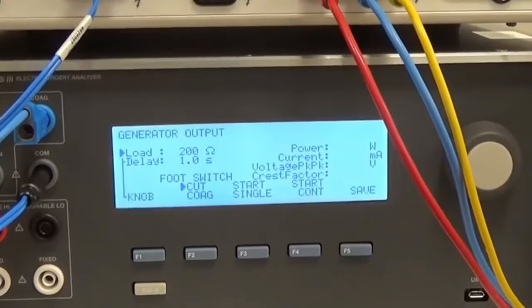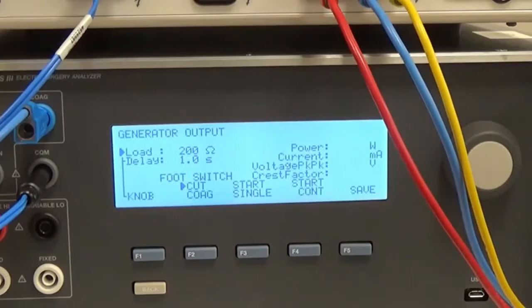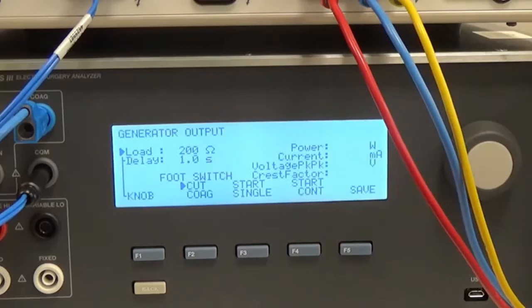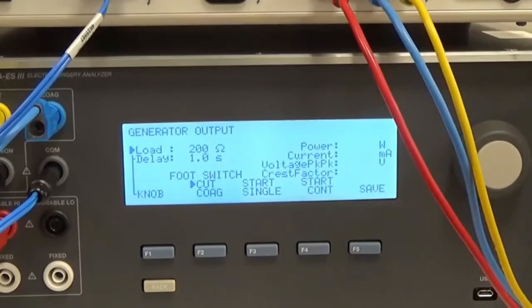Fluke recommends that you use 200 ohms for a load when doing this testing, and they recommend that the delay is 1 second. Some other options you have, you can do a cut or coag depending on what type of test you want. You can do a start single test or a start continuous test. And last, you can save your data on the right.